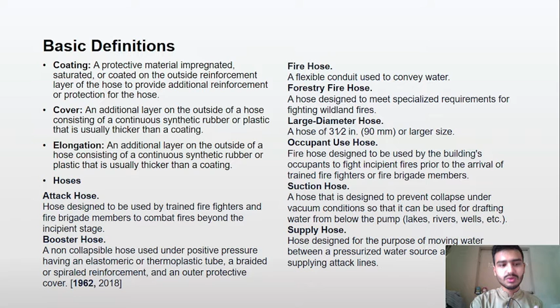Now come to the design requirements according to the NFPA rule 1961. The design requirement for attack hose is basically the test pressure. The minimum design test pressure for attack hoses should be 300 psi or equivalent to 20.7 bar. Attack hose shall withstand a test pressure of 2 times its design service test pressure without movement of coupling, leakage or breakage of any thread in the reinforcement when subjected to the proof test.